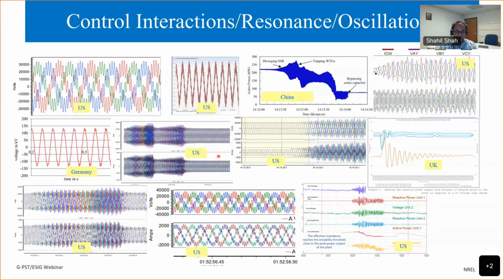Not only the economic impact, they also impact reliability. For example, on this right side, you see subsynchronous oscillation in another offshore wind power plant in the UK, which played some role in a countrywide blackout in August 2019. So we need to understand these oscillations or the small signal stability issues. As power system engineers, we try to classify them depending on the frequency or depending on which equipment is involved. We call it subsynchronous oscillations, subsynchronous resonance, harmonic oscillations, control interactions. But basically they are all the same. The classification helps because many times for that particular problem, the mechanisms are common, but sometimes it also creates confusion because the reasons behind these oscillations tend to overlap.